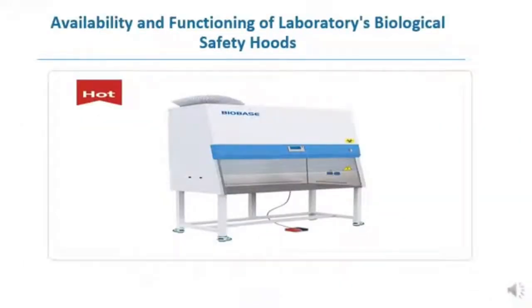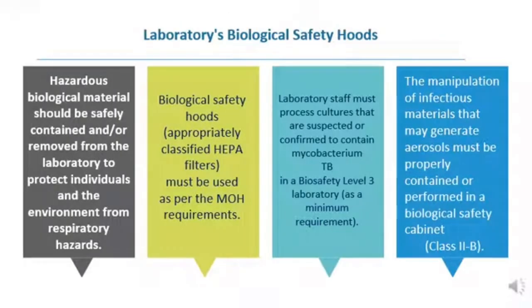The third substandard of this standard is the availability and functioning of the laboratory biological safety cabinet. When exploring the laboratory biological safety cabinet, we focus on the following: hazardous biological material should be safely contained or removed from the laboratory to protect individuals and the environment from any respiratory hazard exposure. Biological safety cabinets with an appropriately classified HEPA filter must be used as per MOH requirements. Laboratory staff must process cultures suspected or confirmed to contain mycobacterium TB in a biosafety level 3 laboratory as a minimum requirement, and the manipulation of infectious material that may generate aerosols must be properly contained or performed in a biological safety cabinet class 2B.